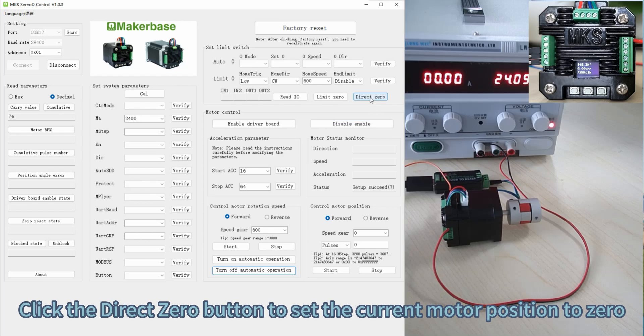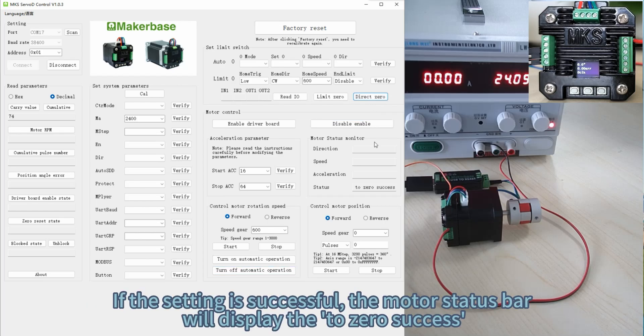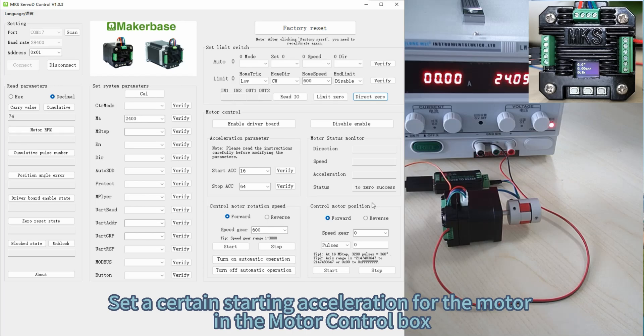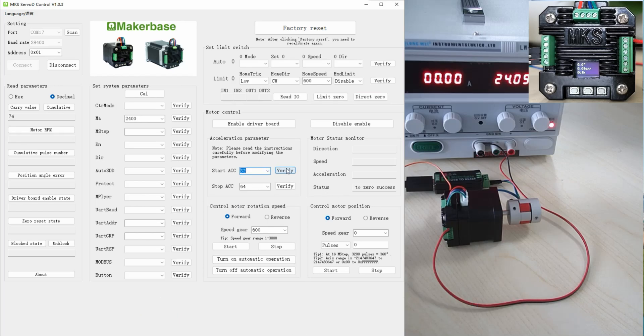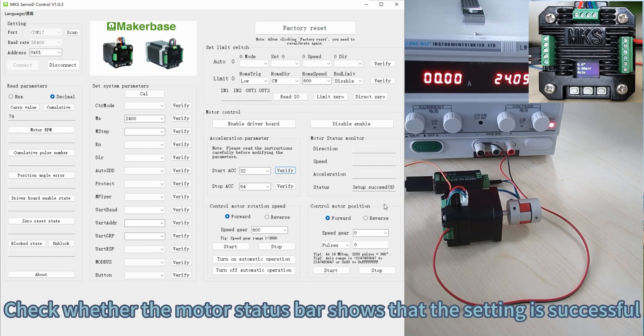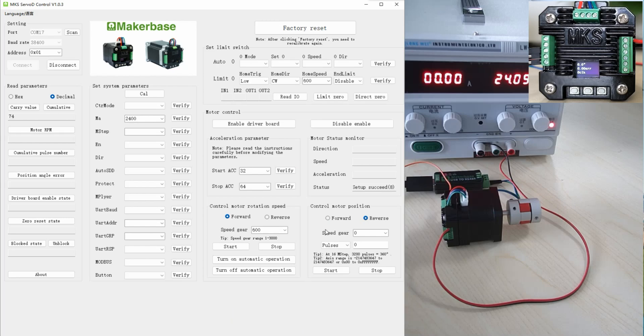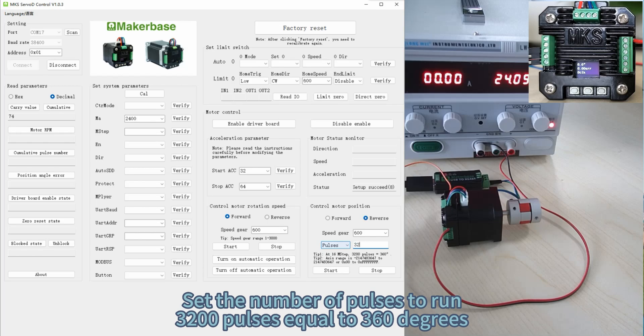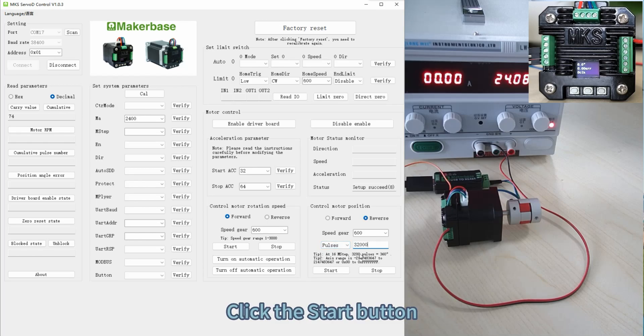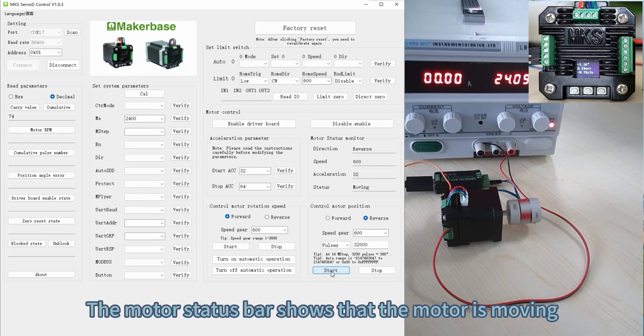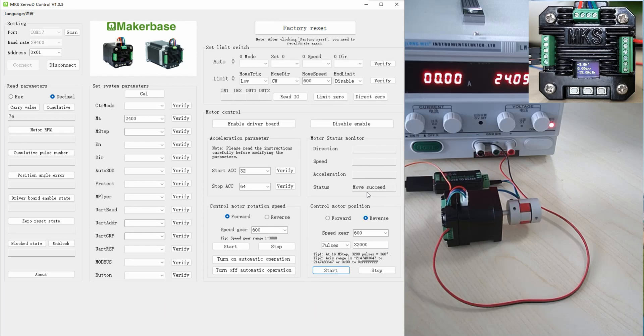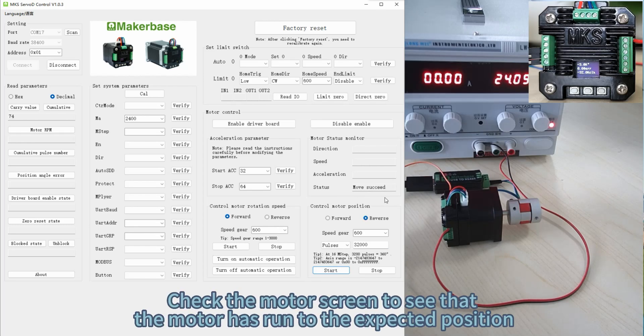Click the Direct Zero button to set the current motor position to zero. If the setting is successful, the motor status bar will display 'return to zero success'. Set a certain starting acceleration for the motor in the motor control box and check whether the motor status bar shows the setting is successful. Locate the control motor position box. Set the direction of motor rotation, the speed gear, select the control mode as pulses, and set the number of pulses to run. Click the Start button — the motor status bar shows that the motor is moving.